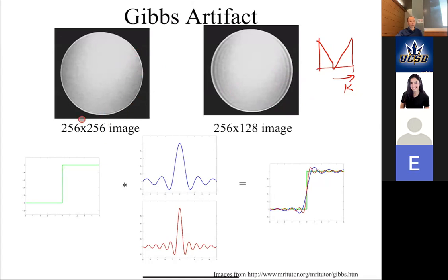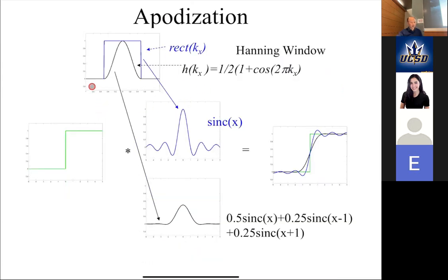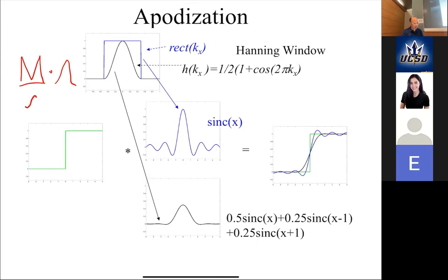So if a technologist sees Gibbs ringing, they could increase the number of phase encodes, increase the matrix size, or many MRI systems will apply some filtering in k-space. Instead of multiplying by a rect function in k-space, you multiply by a smoothing filter — so instead of a sinc function you get a nicer function. You will never see an option for a Ram-Lak filter on an MRI console. On CT, yes, but in MRI that's generally not something you'd want to do.